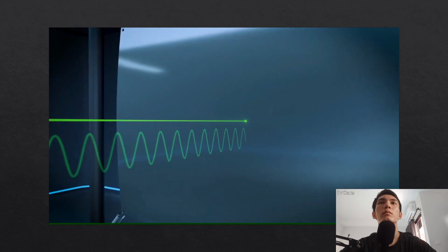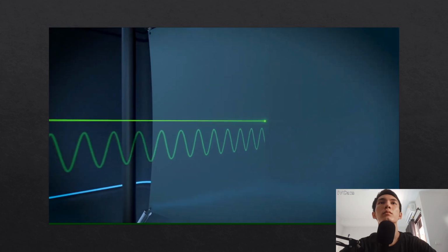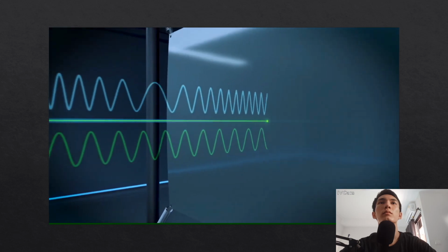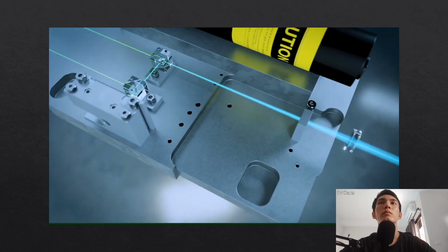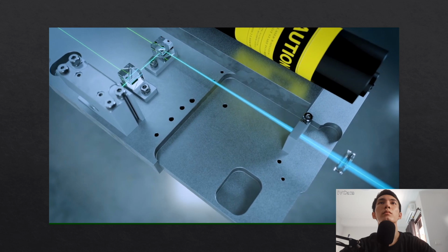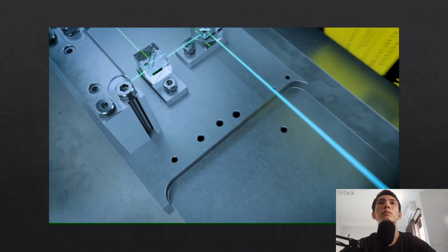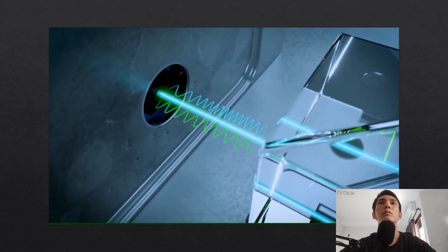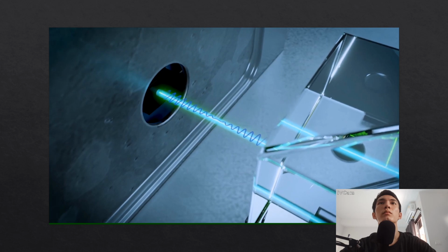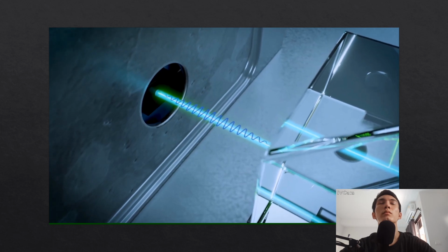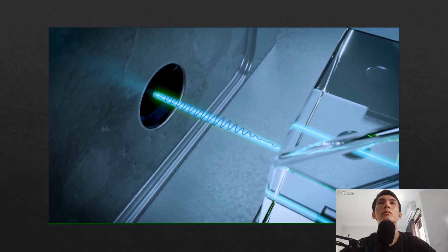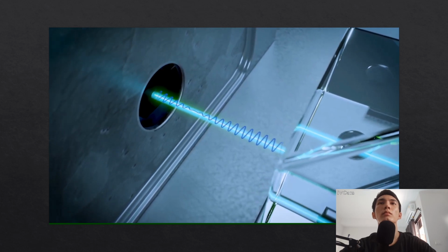Depending on the velocity and displacement, the backscattered light is changed in frequency and phase. The characteristics of the motion are completely contained in the backscattered light. The superposition of this light with the reference beam creates a modulated detector output signal, revealing the Doppler shift in frequency. Signal processing and analysis provides the vibrational velocity and displacement to the test object.